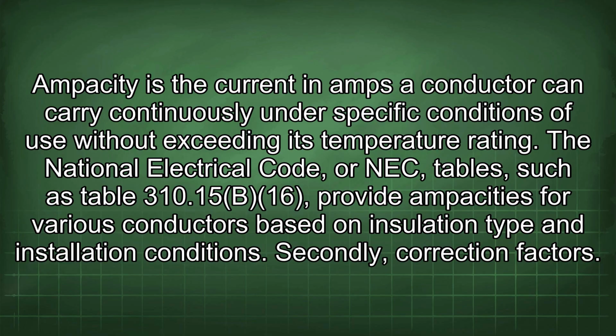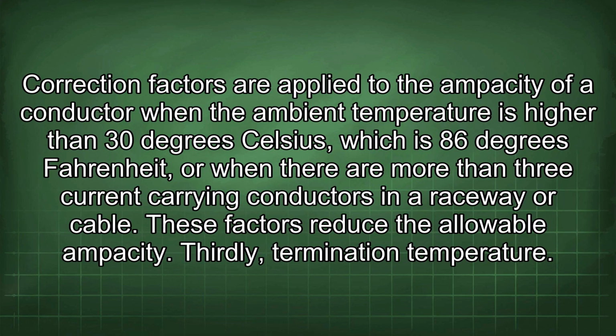Secondly, correction factors. Correction factors are applied to the ampacity of a conductor when the ambient temperature is higher than 30 degrees Celsius, which is 86 degrees Fahrenheit, or when there are more than 3 current-carrying conductors in a raceway or cable. These factors reduce the allowable ampacity.